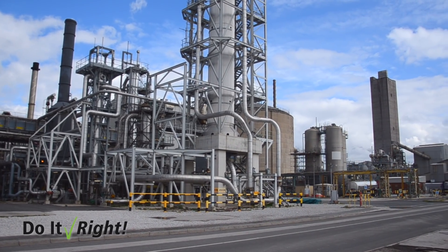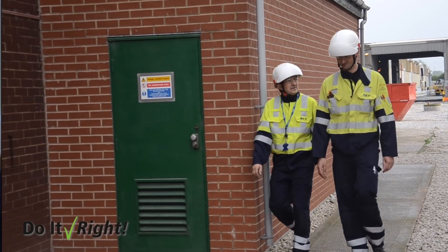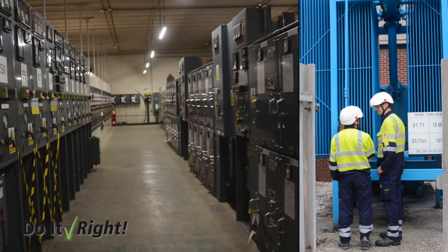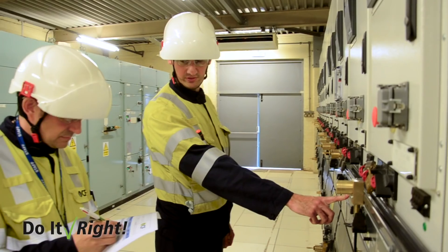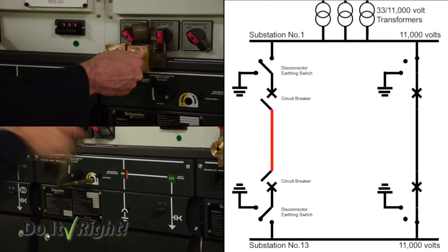There's lots of maintenance we carry out on a weekly basis with the switchgear, so there are various steps we have to take in these isolation processes. We've got 20 substations on site, every one of them has two supplies — so even when we isolate the normal supply, we've got the potential for another supply as well. You can quite easily have one feed on and one feed off, and if you do something in the wrong order, something becomes live that shouldn't be. We've got step-by-step switching procedures — not just step-by-step, but step-by-step in this specific order.